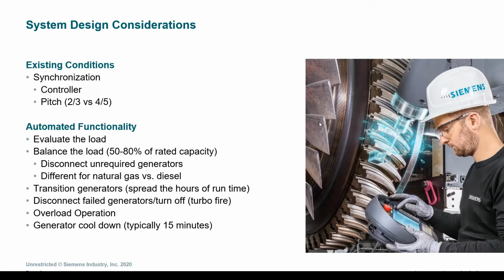Also, it is important at the beginning of the project to review the submittals and ensure that the generators have the transition runtime programmed into them, which allows the generators to spread the hours across each of the generators. So for instance, if you have an N+1 redundancy, generator 4 is not always the redundant generator and thus not being utilized. We want to make sure those hours are spread as evenly as possible across those operations. Additionally, if a generator does fail, whether it's due to maintenance or an emergency condition such as the turbo starting on fire, it automatically disconnects from that emergency bus.